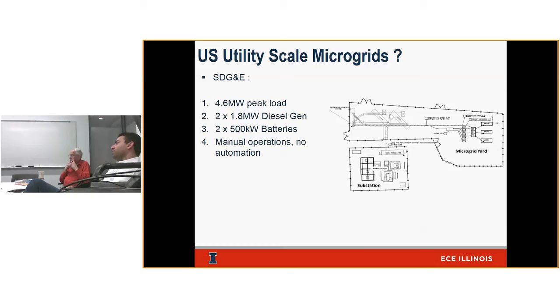All manual operations. So what would happen is if you lose that line, they'll send a troubleman to the substation, fire up the diesel gensets, then make sure the batteries are turned into a voltage source by pushing a button, and try to parallel those together. Once he's sure they're both paralleled, all manually, he'll actually close the breaker for one.